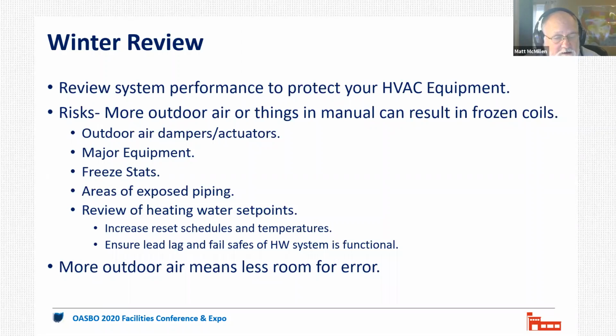Also important, especially in the Midwest and the winters we have with the potential of freezing, is that your hot water system has been pre-tested, things you would normally do seasonally to make sure the lead lag, failover sequences, alarm annunciation, those sort of things are tested so that your system will respond appropriately if there's a failure of some sort.